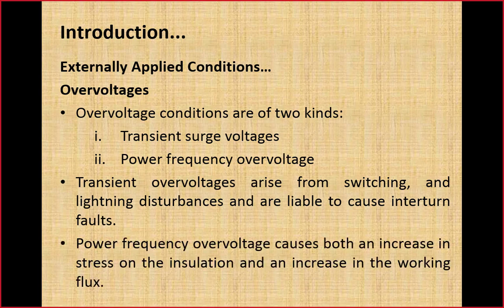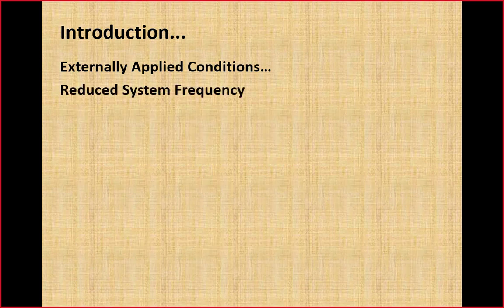So power frequency over voltage causes both an increase in stress on the insulation and an increase in working flux, over excitation. Flux will increase, so due to that increase in flux, transformer core may get saturated. So this is a problem of over voltages. Next we discuss reduced system frequency.